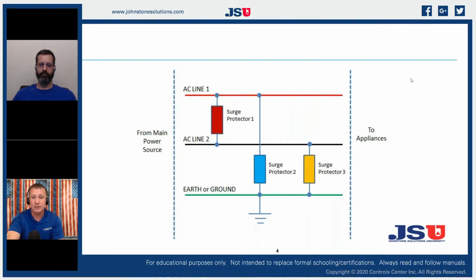So if we look at this particular one, this would be more like our one going to an outdoor unit. We can actually stage these and have multiple surge protectors, multiple MOVs. So in this particular situation, we've got a MOV going between line 1 and line 2. We got an MOV going between line 1 and ground or earth, and then we have one between 3 and earth, so that we have multiple paths. So wherever that high current surge is happening, we can direct it, because we can also use these in this type of a scenario. We can also use this to control small spikes in voltage.